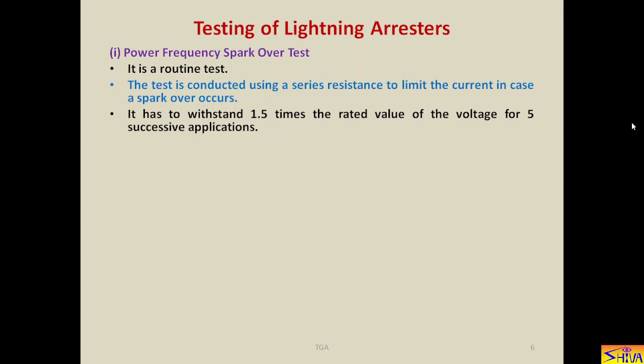It has to withstand 1.5 times the rated value of the voltage for 5 successive applications. It has to withstand, because during power frequency over voltage the lightning arrestor should not spark over. So we apply 1.5 times the rated value of the power frequency spark over voltage, and it must withstand 5 successive applications. It should not spark over. This test is done under both dry and wet conditions.